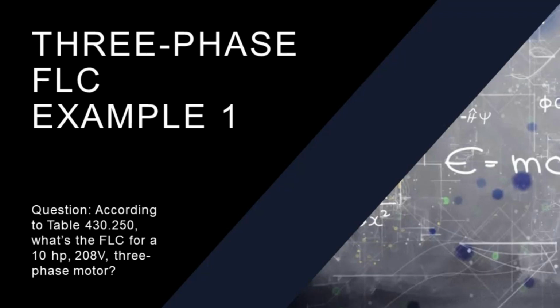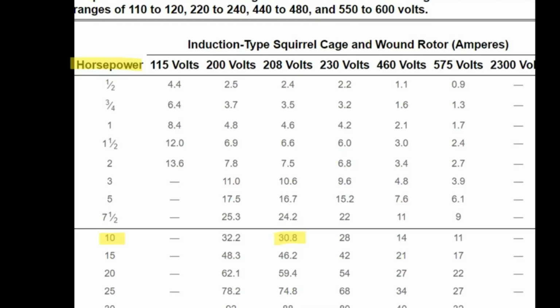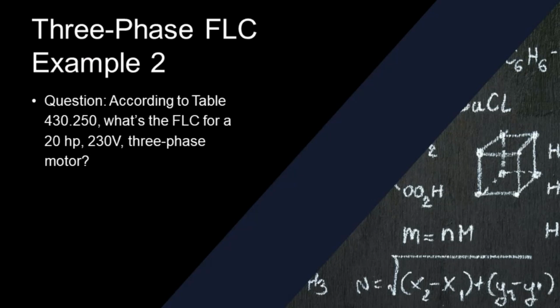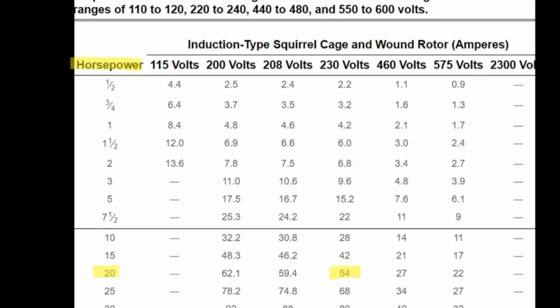Okay, according to Article 430.250, what's the full load current for a 10 horsepower 208 3-phase motor? Okay, so now again I'm on table 430.250. My horsepower is 10. I go over to 208. I'm at 30.8. So that's the FLC code book for that motor. All right, another FLC example. According to table 430.250, so again 3-phase, what is the FLC for a 20 horsepower 230 volt 3-phase motor? Here we are. 20 horsepower, 230 volt, 54. Okay, pretty easy table to use.